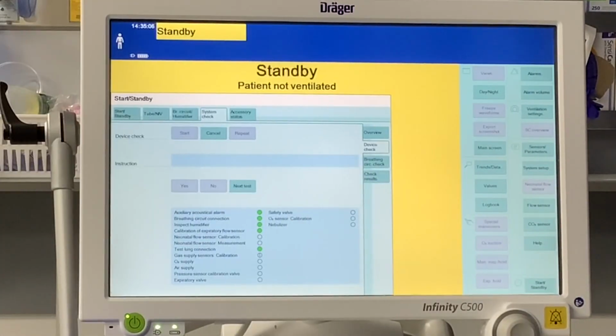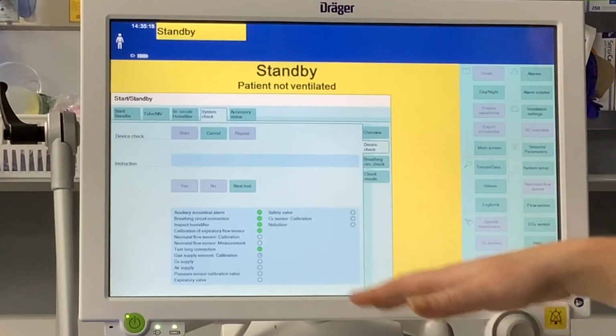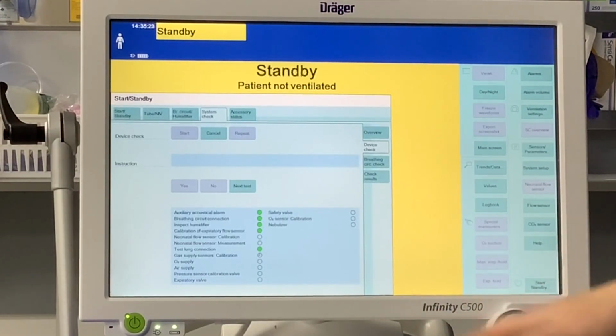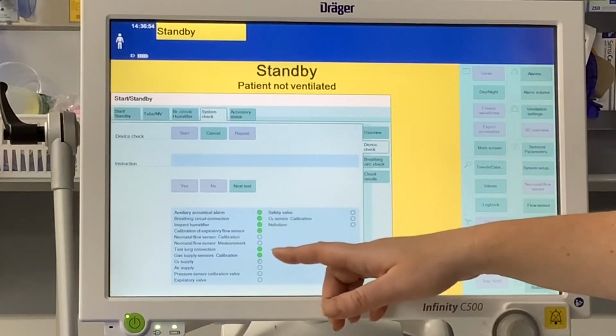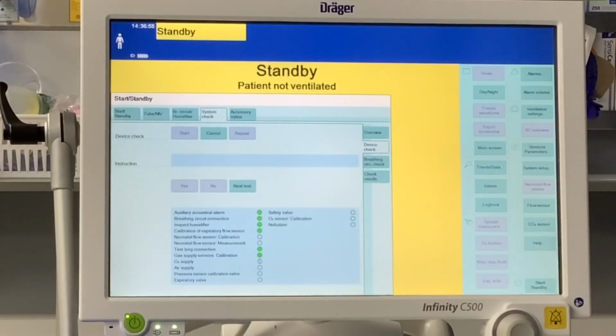This is probably the time that when it's doing this, I might go grab an end-tidal CO2, the ones for the ventilator, and put it on top of here. This vent doesn't have one on it, but also I might put an inline suction catheter on top just while I'm waiting. And the vent will make noises. That's all normal. And once it's done the gas supply sensor calibration, it will start going through the rest of the test itself. And now you'll see it's done. So once it's done, it starts doing the rest of the checkout all by itself.